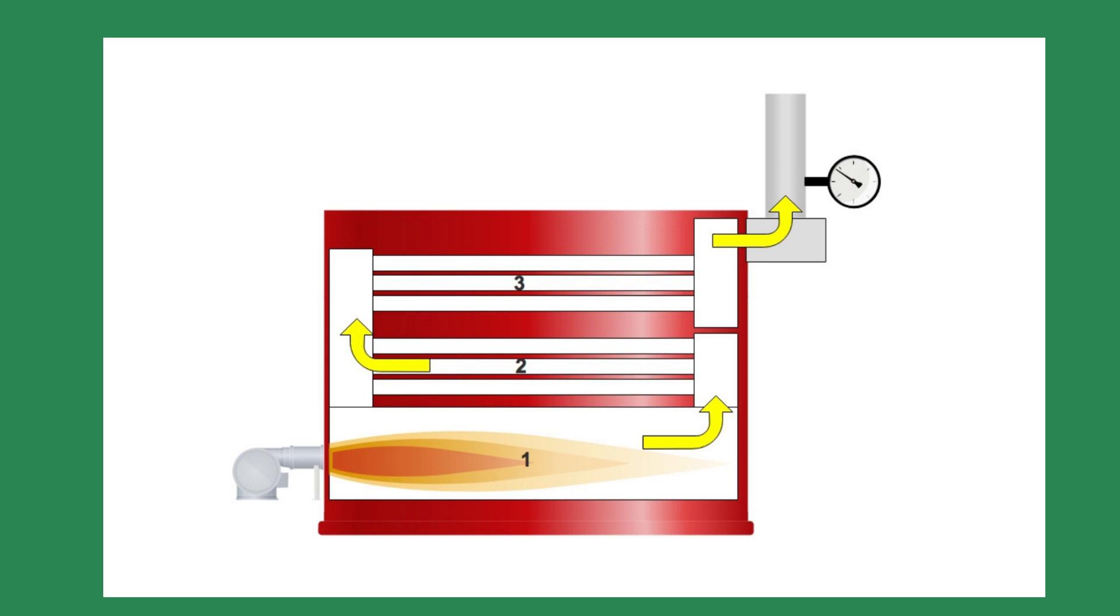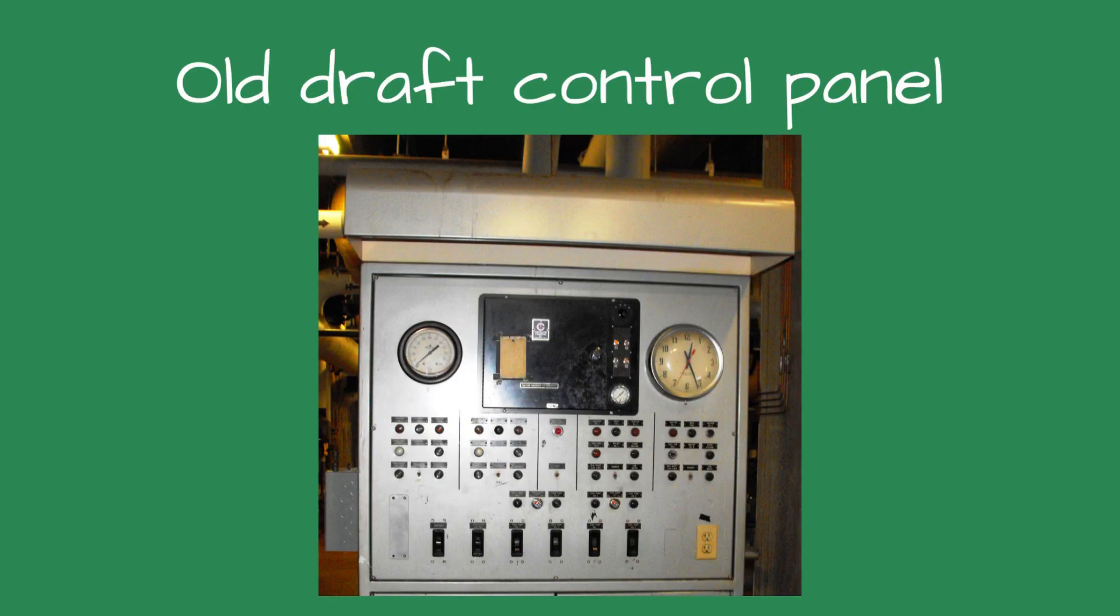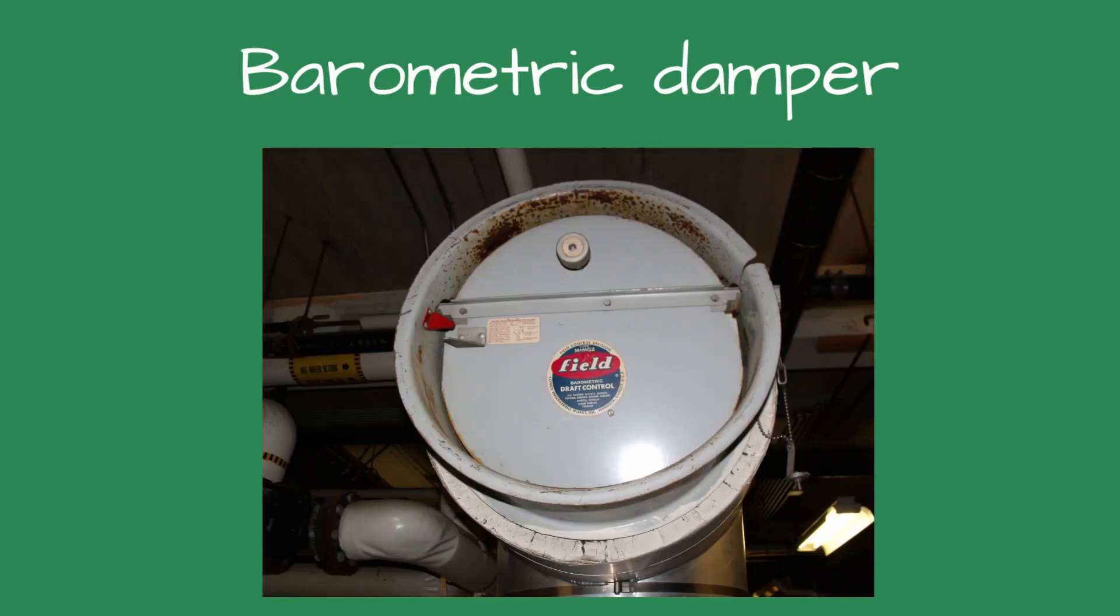It will eventually break. The boiler requires a stable environment, and the chimney is like the wild child. Most older boilers were designed to have a draft at the boiler outlet to be about minus 0.05 inches water column. The draft conditions inside the chimney could cause negative conditions of 10, 20, or even 100 times that amount. How do you handle these erratic swings?